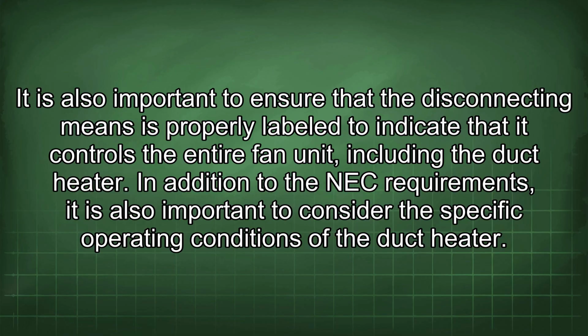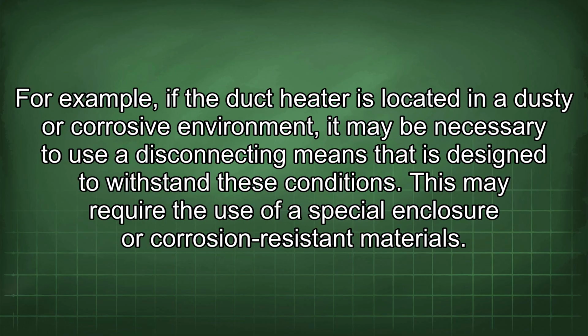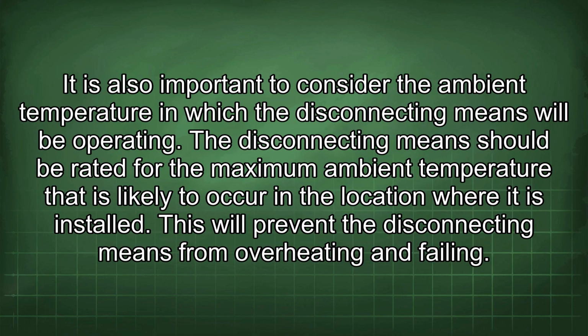In addition to the NEC requirements, it is also important to consider the specific operating conditions of the duct heater. For example, if the duct heater is located in a dusty or corrosive environment, it may be necessary to use a disconnecting means that is designed to withstand these conditions. This may require the use of special enclosure or corrosion-resistant materials. It is also important to consider the ambient temperature in which the disconnecting means will be operating. The disconnecting means should be rated for the maximum ambient temperature that is likely to occur in the location where it is installed. This will prevent the disconnecting means from overheating and failing.